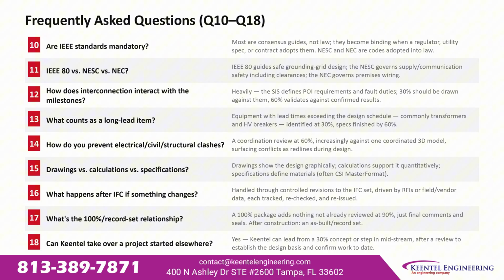Are IEEE standards mandatory? Most are consensus guides that become binding when adopted by a regulator, utility specification, or contract. NESC and NEC are codes adopted into law and are mandatory. What is the difference between IEEE 80, NESC, and NEC? IEEE 80 guides grounding grid design. The NESC governs supply and communication system safety, including clearances. The NEC governs premises wiring. All 3 commonly apply to the same project.